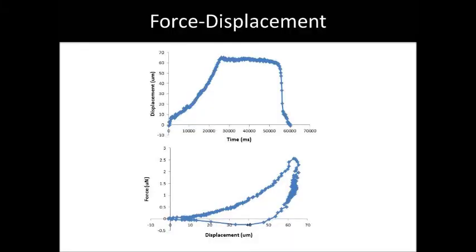Rabia, can you tell me a little bit more about the test results you're getting and why you find them interesting? Absolutely. So one of the tests that we acquire is the force displacement curve or the stress-strain curve if you normalize the area. So essentially what the micro squisher does is it has a ramp function seen here where you can compress the sample, hold the sample, and then decompress the sample which is called the recovery phase. And then this sort of test produces a typical stress-strain curve seen here where you can observe the hysteresis of our viscoelastic samples.